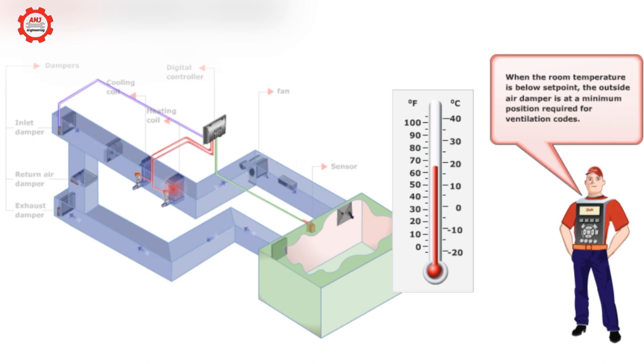When the room temperature is below set point, the outside air damper is at a minimum position required for ventilation codes.